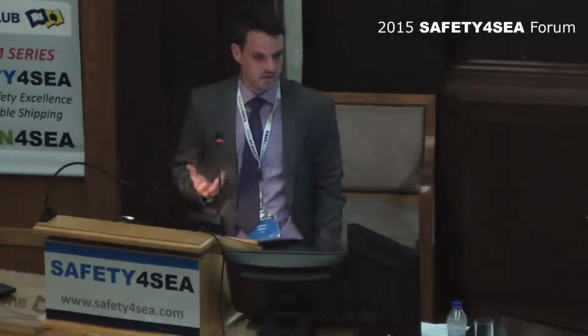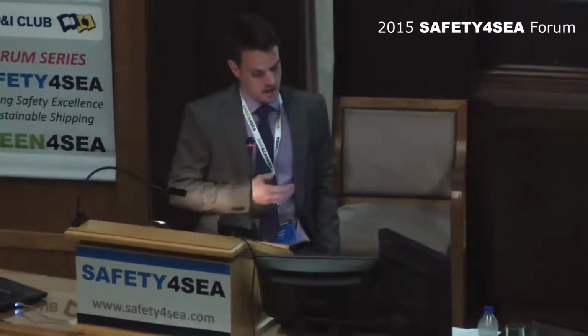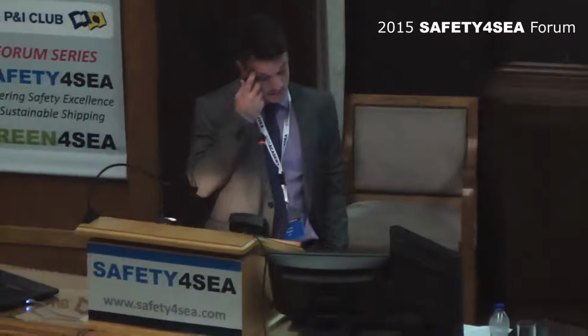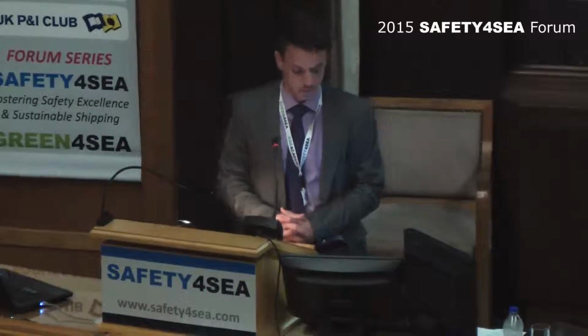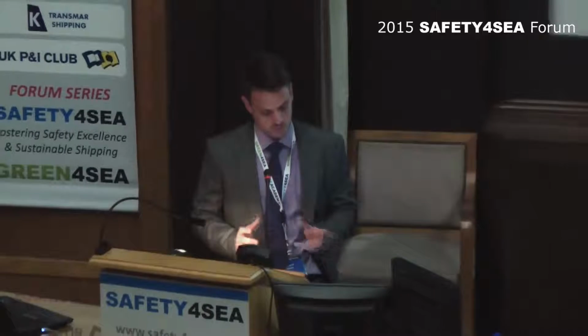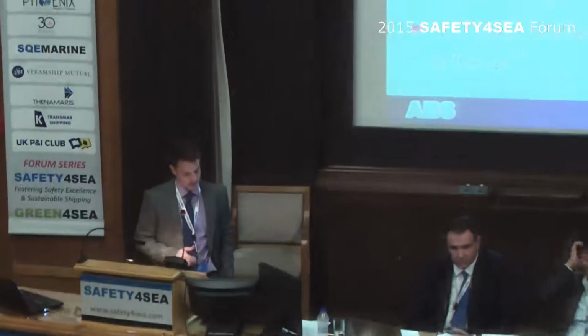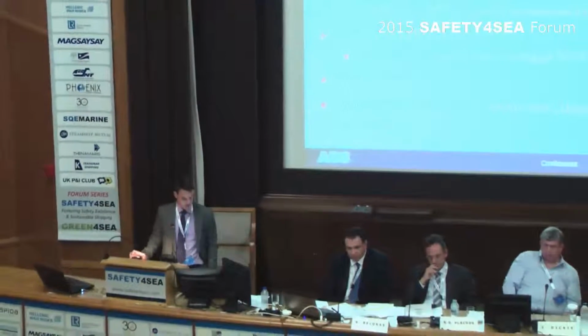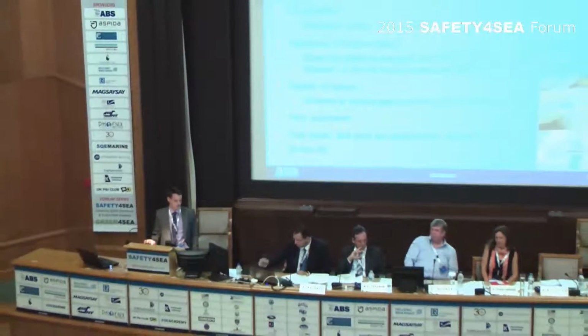Starting with the properties of LNG, we call it a refrigerated gas. LNG comes out from a treatment where the natural gas is treated and then liquefied. In order to be kept in the liquid state, it needs to be kept very cool, because its boiling point at atmospheric pressure is minus 162 degrees Celsius. It's of course flammable. The limits are between 4.5% and 15% per volume in air. It's colorless, nearly odorless, non-corrosive, non-toxic, but it can act as an asphyxiant in enclosed spaces.